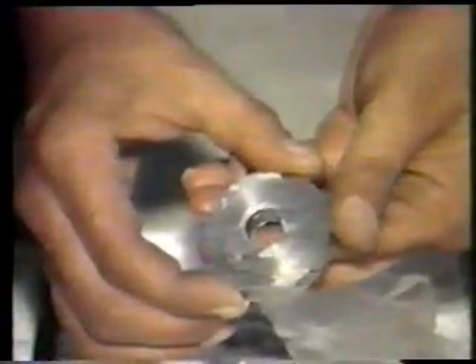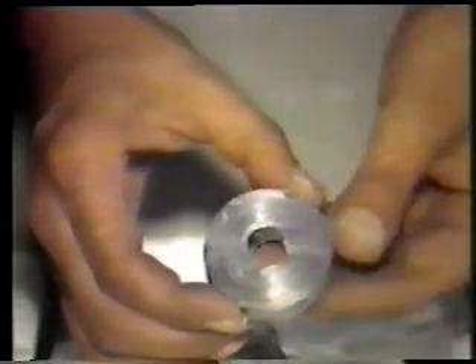Place the end of the valve with the detent cage inside a small box and remove the cage and plunger from the valve. Be careful not to lose any of the balls and springs as the detent cage is removed from the valve. With your fingers, push the plunger assembly toward the detent cage assembly of the valve. Remember, remove the detent assembly cage and the plunger at the same time. Notice the holes for the springs on the side of the detent cage. Note, there are 2 different types of detent cage assemblies. There is no way to distinguish which is in the valve from the valve's exterior appearance.